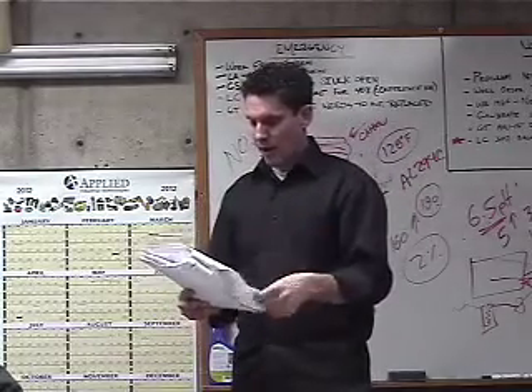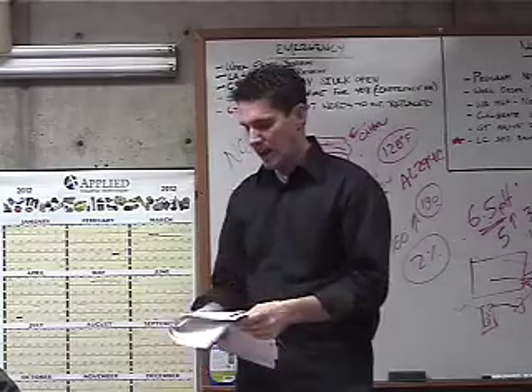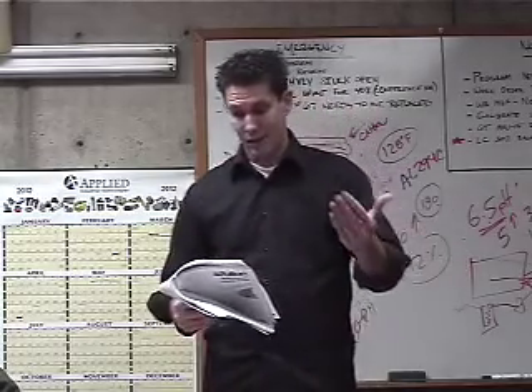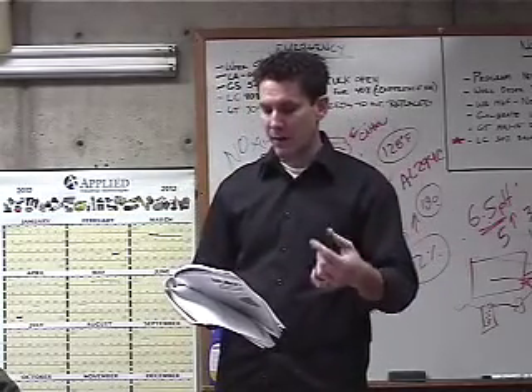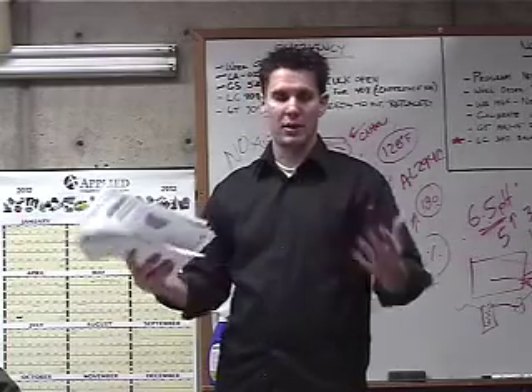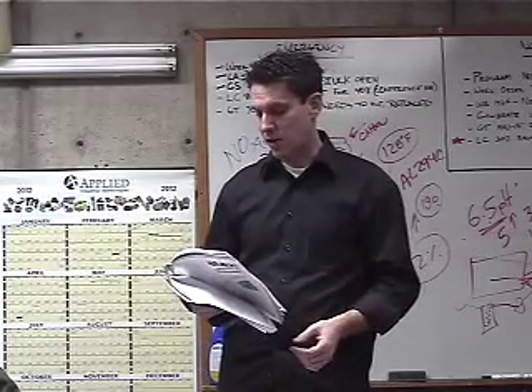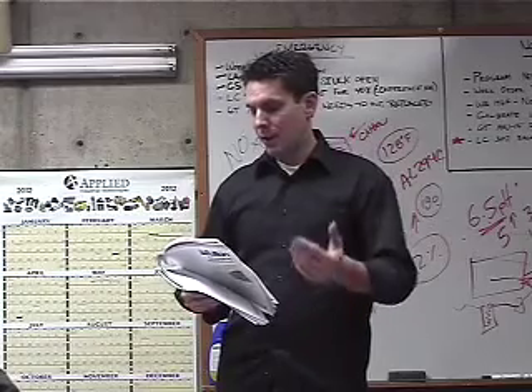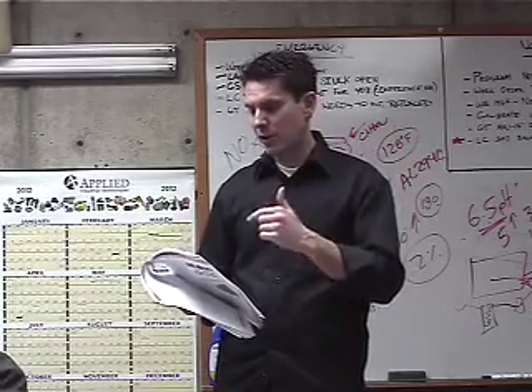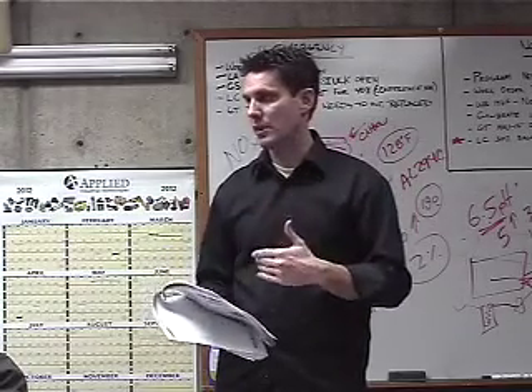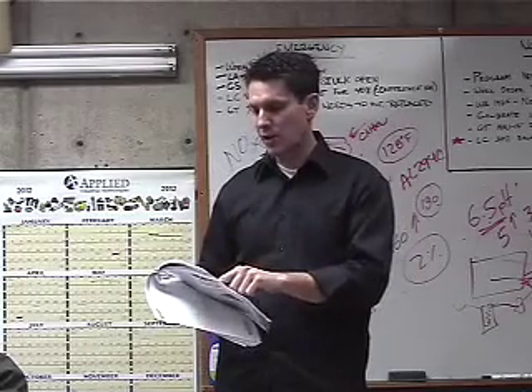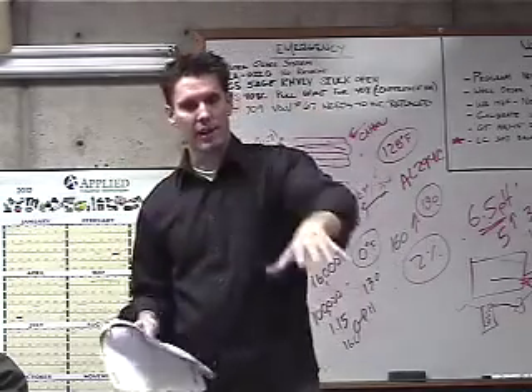All right, so first of all, the daily maintenance schedule. They want you to inspect this daily, but just make sure that the temperature and the general conditions around the boiler are fine. Make sure that the flow of combustion and ventilating air to the boiler is not obstructed, so check for any obstruction.